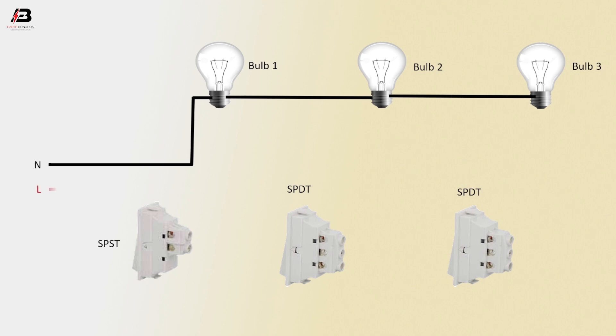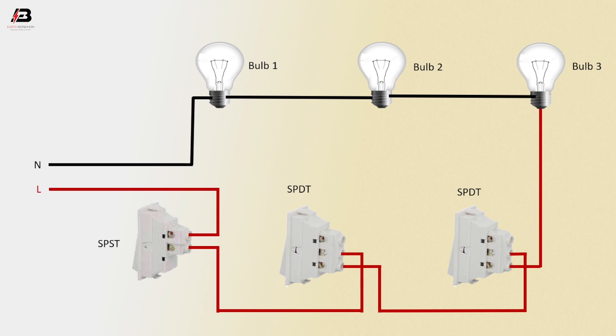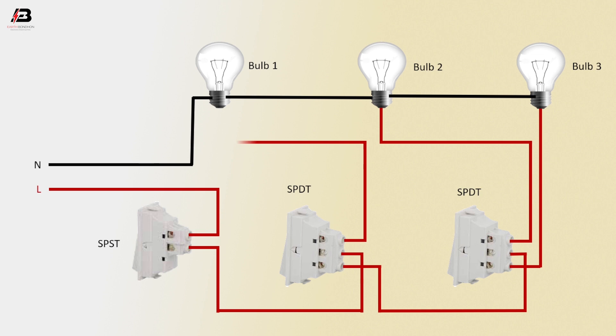Phase connection to the SPST switch. Phase connection from the SPST switch to connect with the SPDT common terminal. Phase connection from the SPDT L2 terminal to another SPDT common terminal. Phase connection from SPDT L2 terminal to Bulb 3. Phase connection from another SPDT terminal to Bulb 2. Phase connection from another SPDT L1 terminal to Bulb 1.